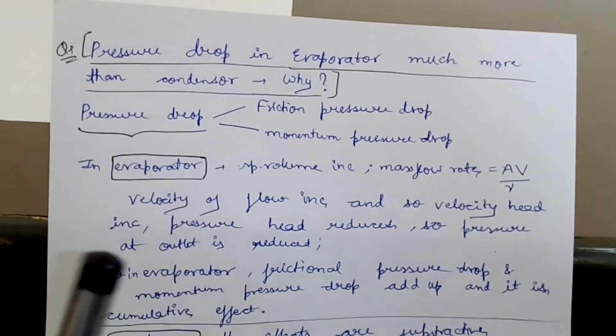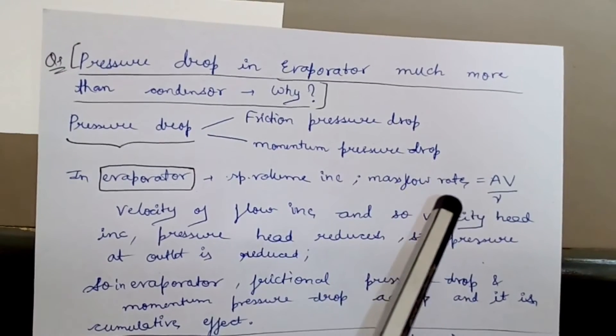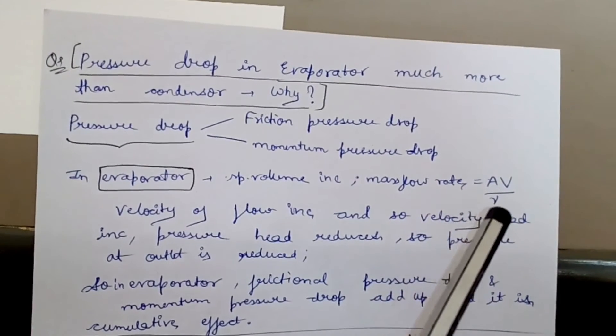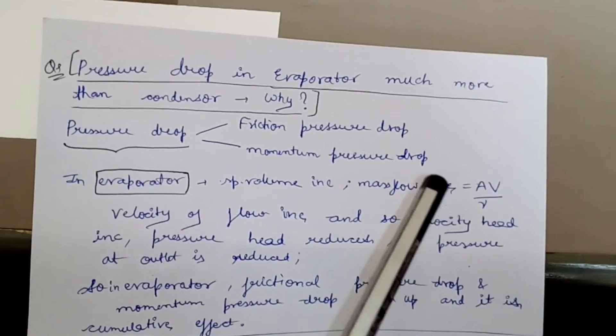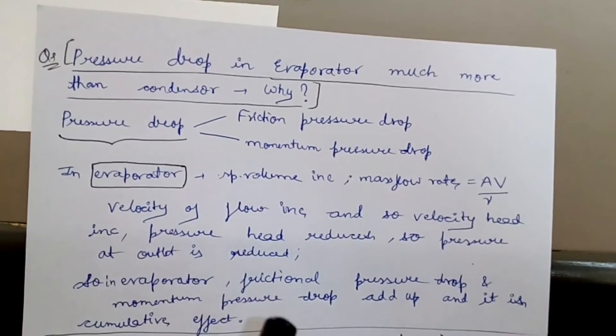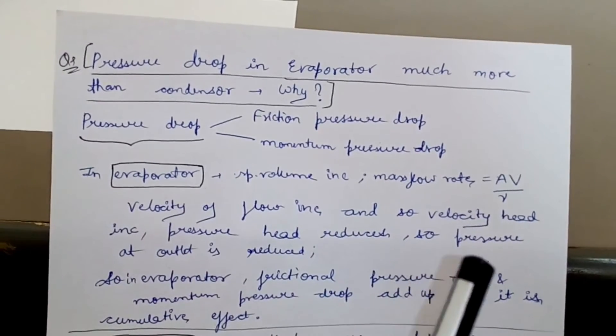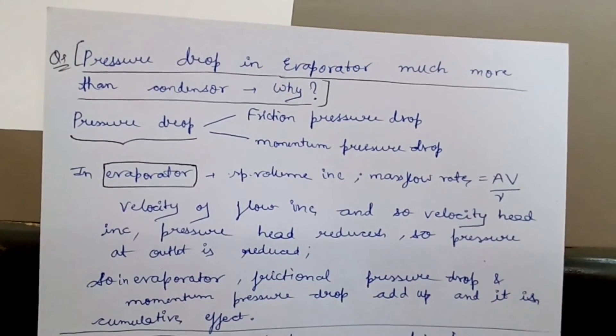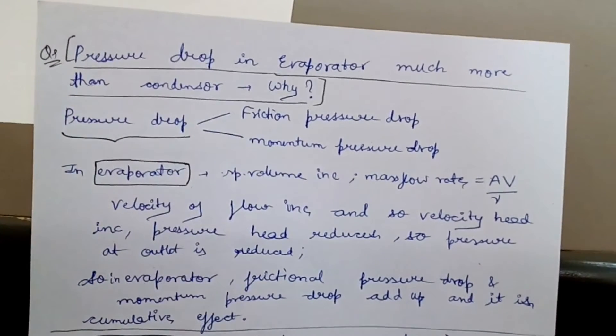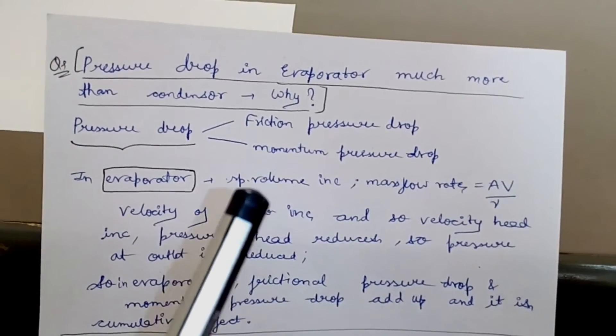In the evaporator, there is vapor refrigerant so specific volume ν is high. Mass flow rate is given by Av/ν, where A is area and v is velocity. If ν increases, velocity must increase to maintain the same mass flow rate. As velocity increases, velocity head increases, and by Bernoulli's equation the pressure head must decrease to keep total head constant — so pressure at the outlet is reduced. We can assume friction pressure drop is roughly the same in both evaporator and condenser; the deciding factor is the momentum pressure drop.